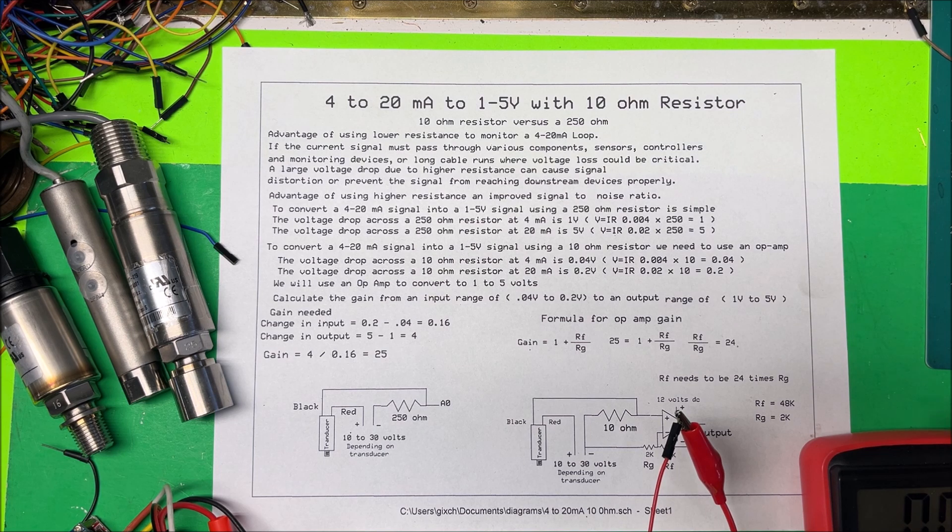Let's take a look at a 4 to 20 milliamp loop and we're going to convert that to 1 to 5 volts. We're going to do it with a 10 ohm resistor. Now the easiest thing to do is use a 250 ohm resistor.